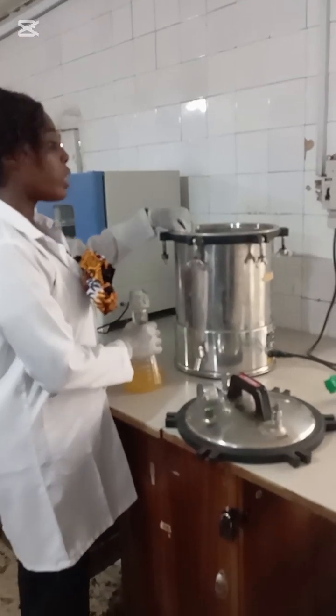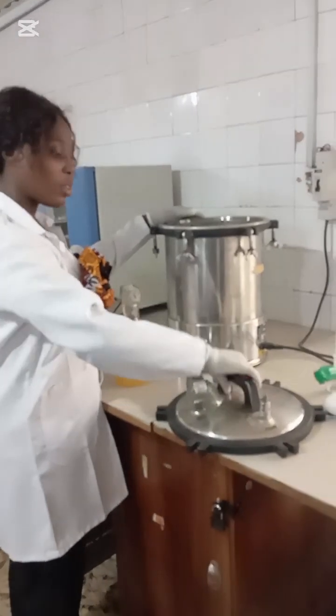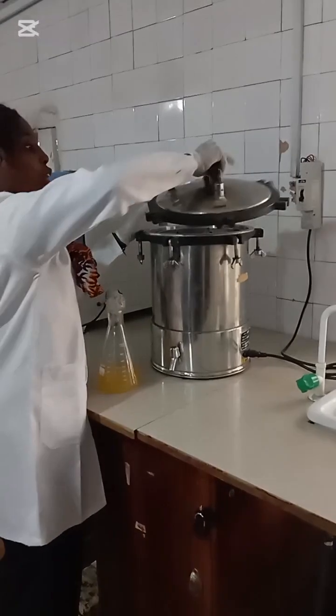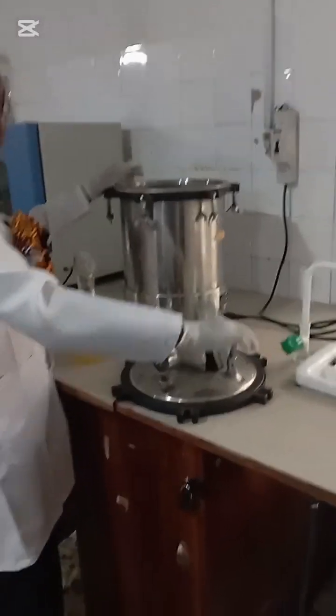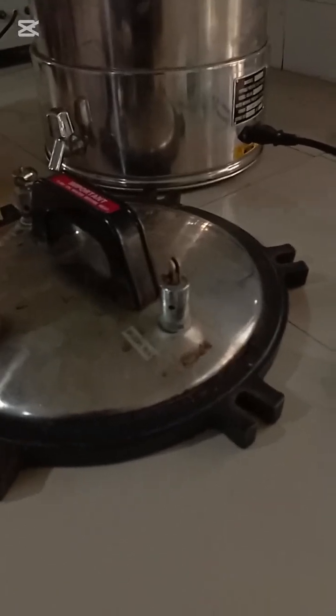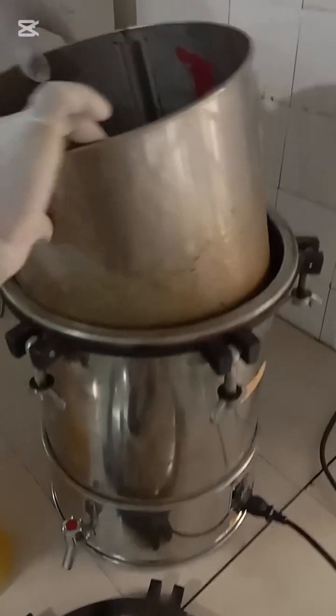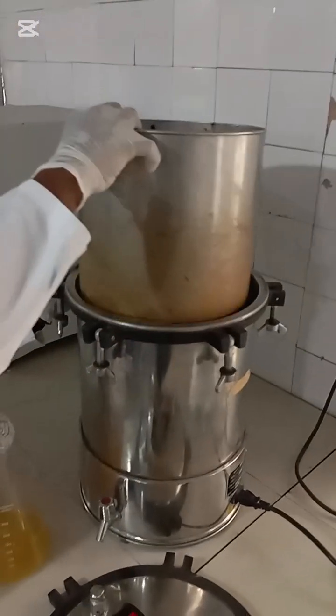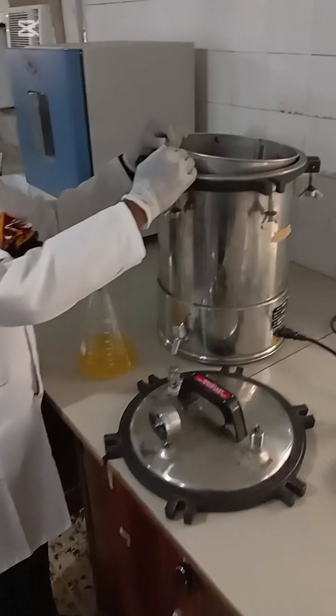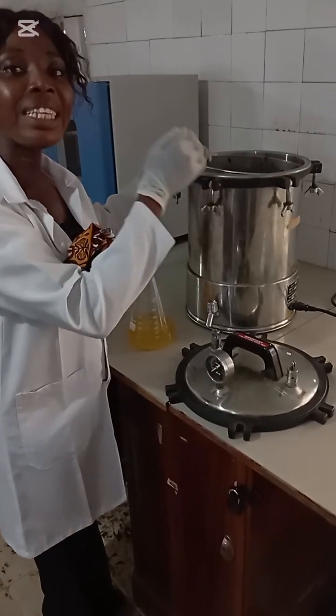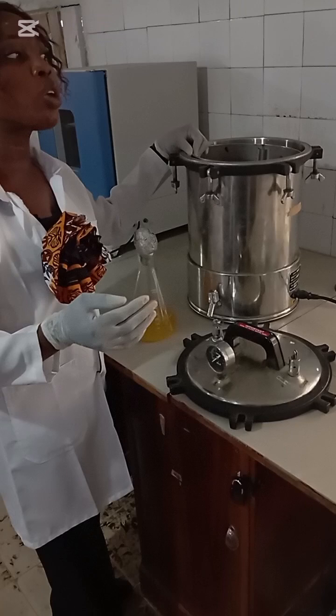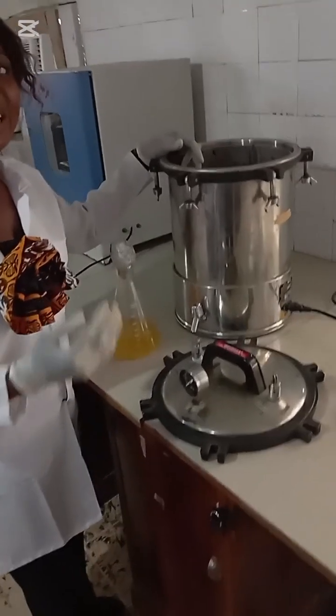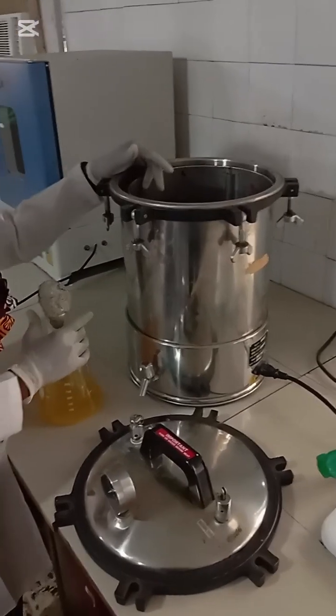So now you see, we are ready to autoclave. This is our autoclave. This is the lid of the autoclave. Now the autoclave has a valve. This is the valve of the autoclave. This is the temperature and pressure gauge. Now this is the basket of the autoclave. It has a heating ring inside with water. Water must cover the heating elements. So before every autoclaving, you check if the water is covering the heating element. So we already added water to the heating element.